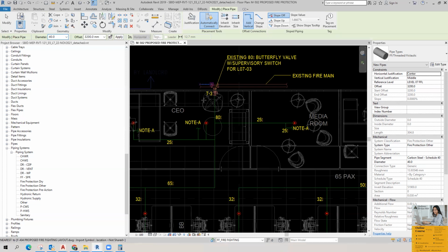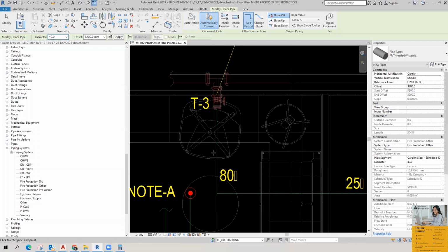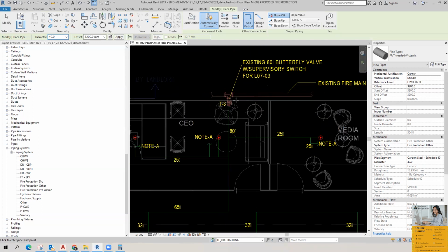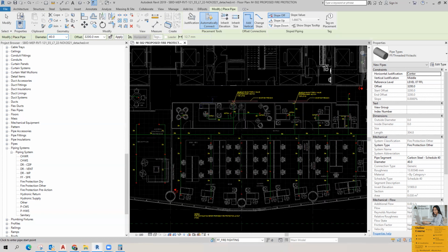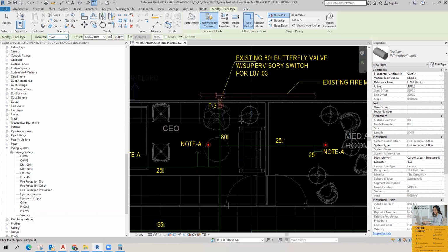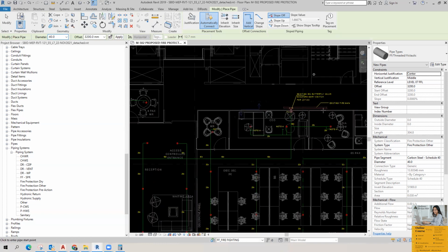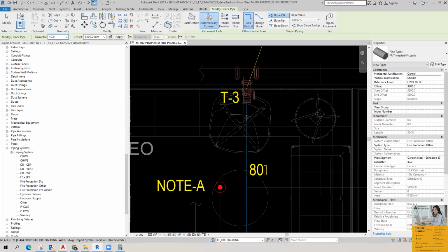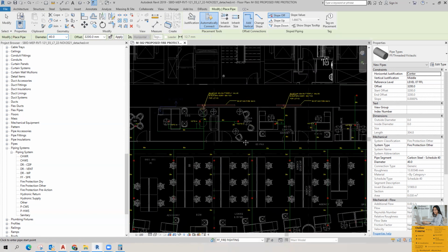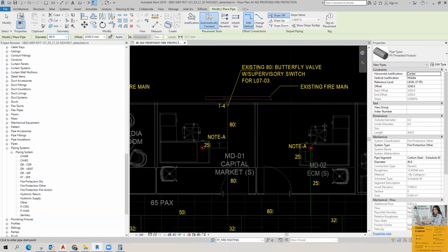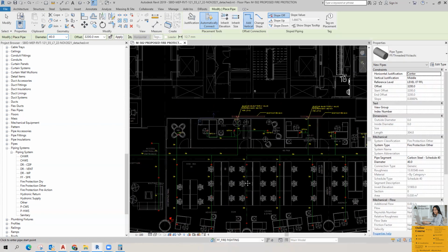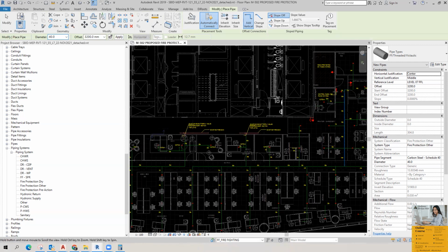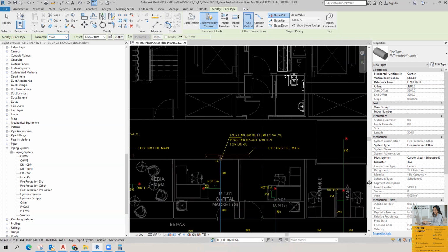Right. That's it. So do one thing. Just provide a zone control valve in the main line, because this zone control valve will be controlling the whole zone, the water of the whole zone. Actually, in our design drawings there is no zone control valve, but please try to provide one in this area and this area, because this is the main line. See, this is a network, right? For every network, we have to provide a zone control valve. So provide one here, also one here.